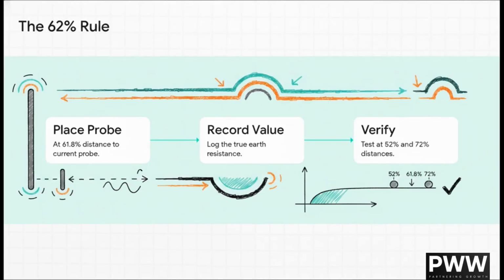Now, finding the true resistance on that curve means you have to avoid the spheres of influence of both the test electrode and that return current spike. So the crucial point is we use what feels like a magic number, the 62% rule. You place your potential probe at exactly 61.8% of the total distance to the current probe. You record that reading, but, and this is key, you do not stop there. You verify its accuracy by moving the probe to the 52% mark and then again to the 72% mark.